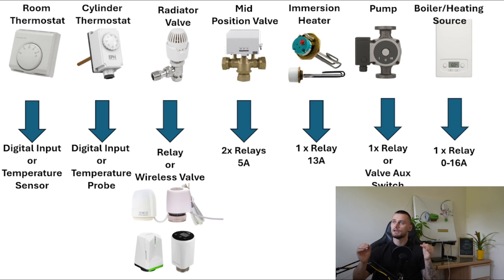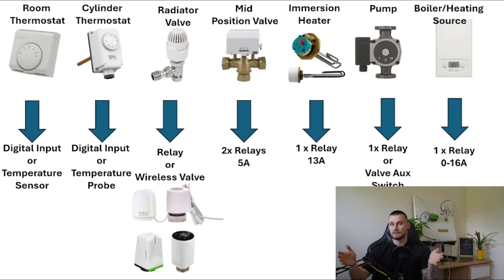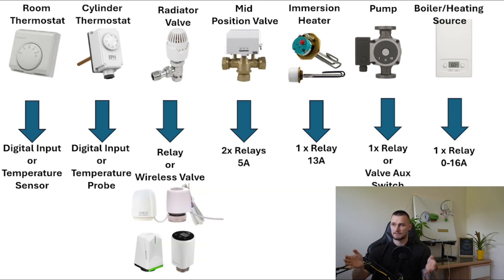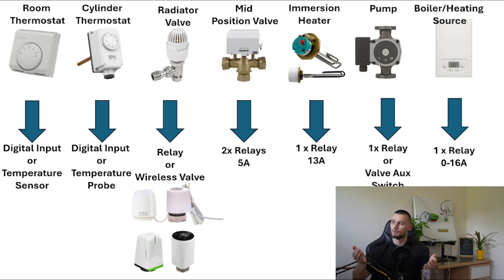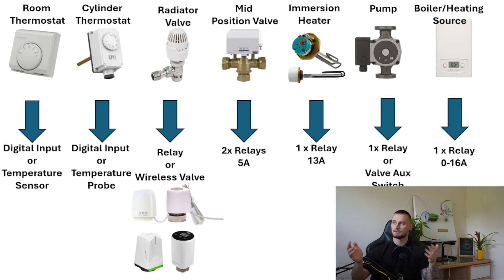If you want full system control, you can replace pretty much every single element. Room thermostats can be any wireless temperature sensor or hardwired if the property allows. The cylinder stat can become an input feeding satisfaction status back into your system. Radiator valves can be replaced with wireless or wired electronic valves. The mid-position valve is again just two relays. The immersion needs another relay, the pump can use a relay or the auxiliary switch of the mid-position valve, and the boiler typically just needs one relay or volt-free contact to call for heat.